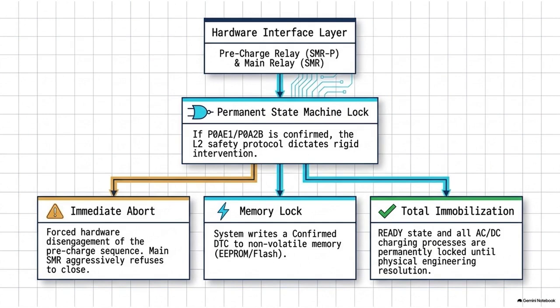Wow. Yeah, the circuit becomes an open loop, it physically breaks, the precharge current drops to zero, and the DC link capacitor remains completely empty. So the system starves because the bypass lane melted, which leads directly into the third failure mode, physical shorts on the load side. This one is brutal.